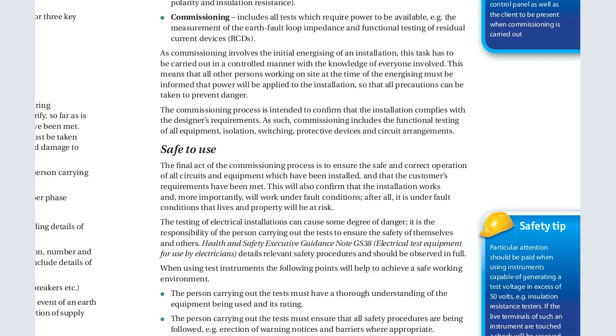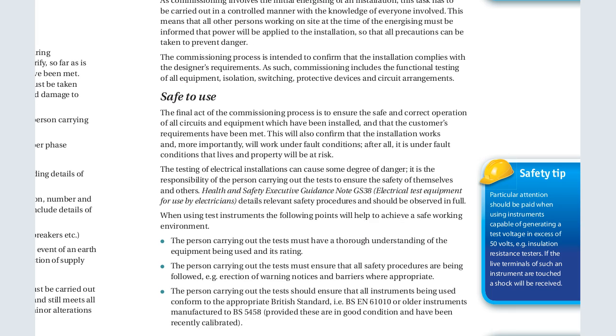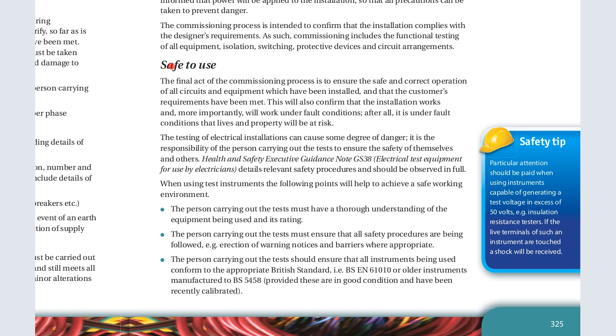Now, safe to use. The final act of the commissioning process is to ensure the safe and correct operation of all circuits and equipment which have been installed and that the consumer's requirements have been met. So this will also confirm that the installation works and, more importantly, will work under fault conditions. After all, it is under fault conditions that life and property will be at risk. So we will go ahead now.